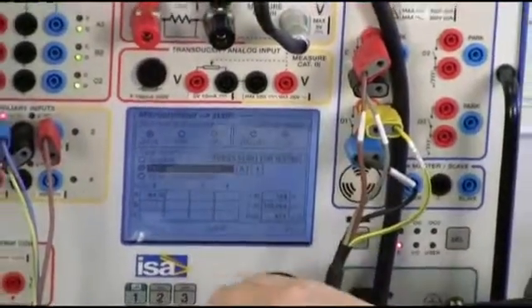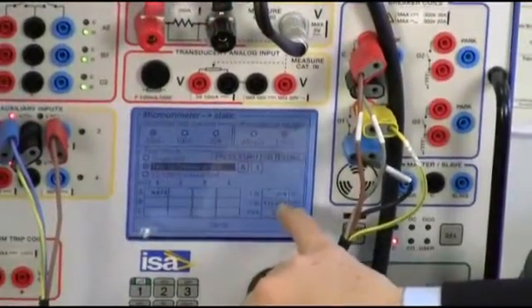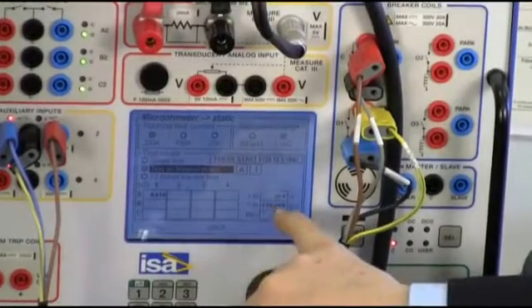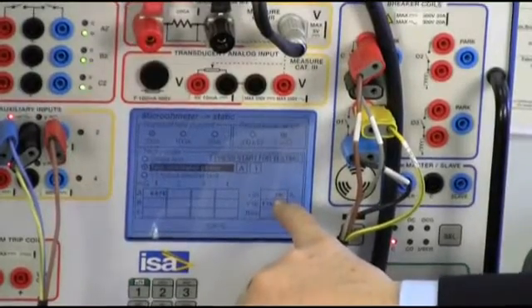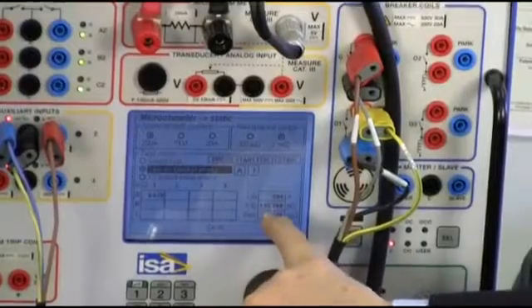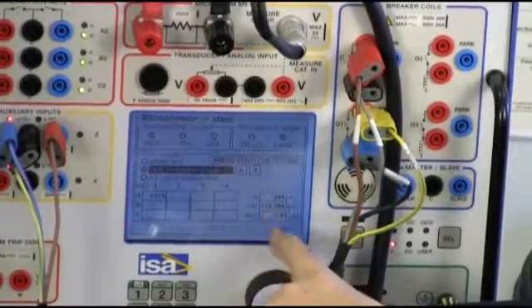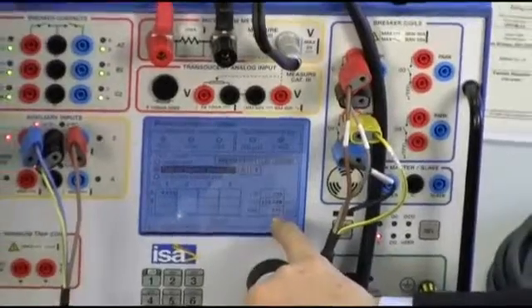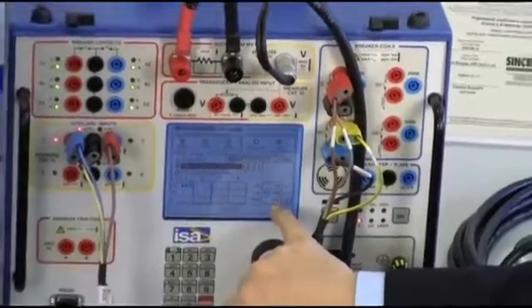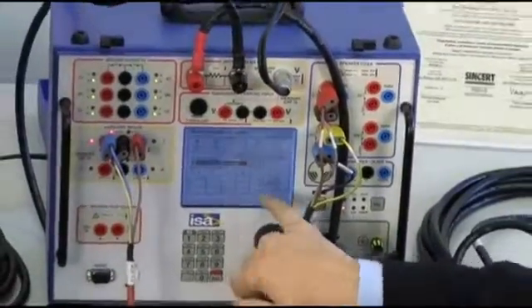Now, I have started the test. It is telling me that the test has been performed, injecting 200 amps, that the voltage drop has been these millivolts, and so therefore, the resistance is 676 micro ohm.